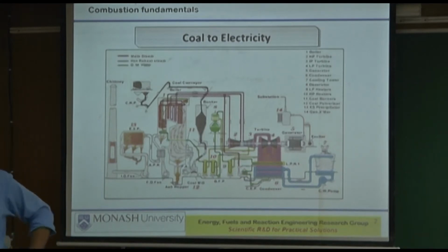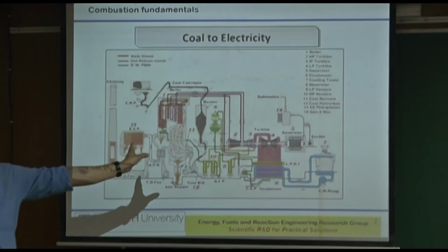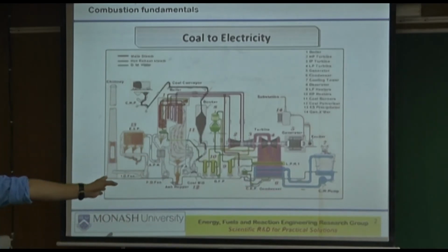So in many countries, there is a lot of anthracite. It can be used for some other purposes, but for power generation, you need a completely different type of boiler design. It's called a down-fired boiler, as opposed to horizontal opposed multi-burners.